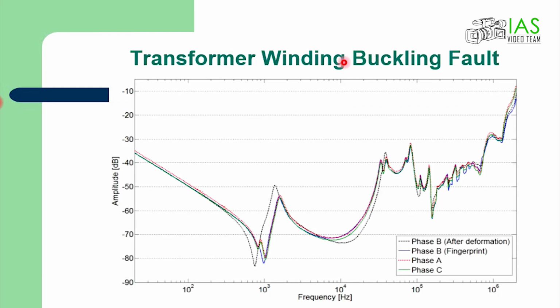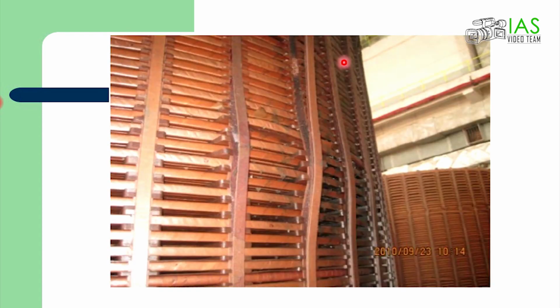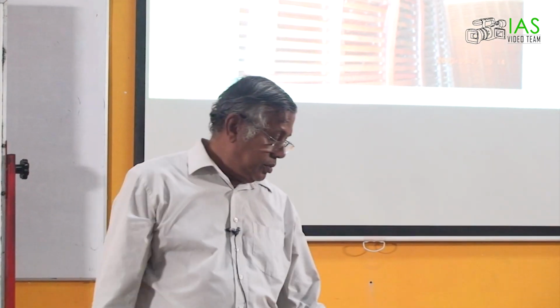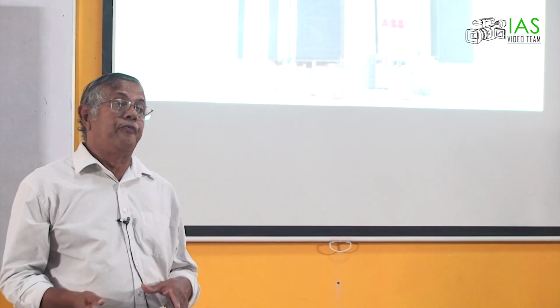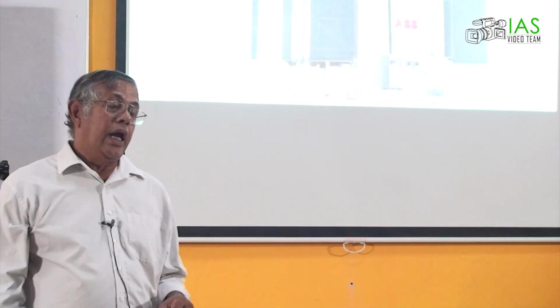So, transformer winding buckling fault, at these frequencies, it gives you the traces apart. Now, this is the fault, buckling of the windings because of the shock. Okay, that is SFRA, that is sweep frequency response analysis.